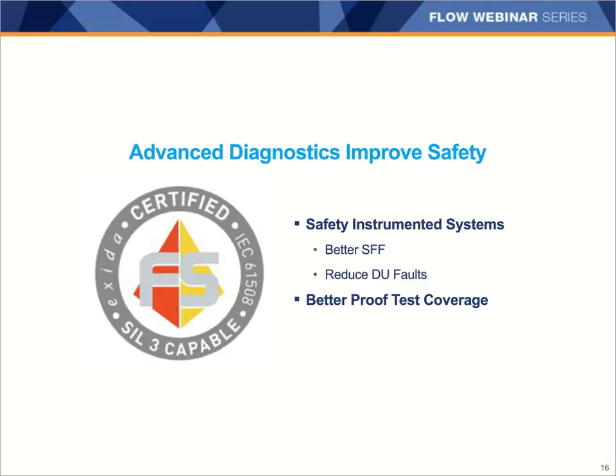Safety instrumented systems have to go through periodic proof tests to make sure that they are still functioning correctly and to reveal potential dangerous undetected failures. Some advanced diagnostics can make the proof testing process a lot easier than traditional calibration tests.